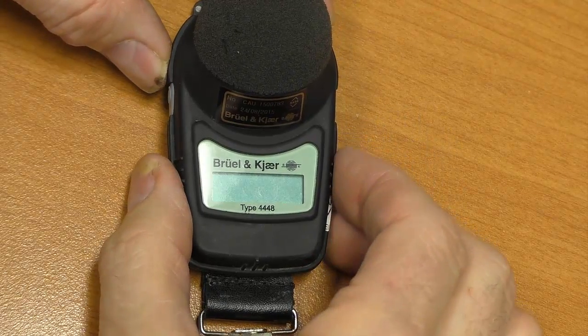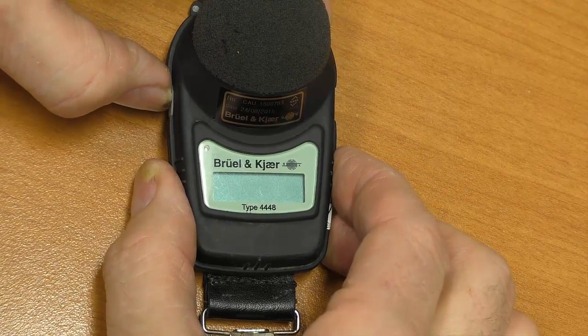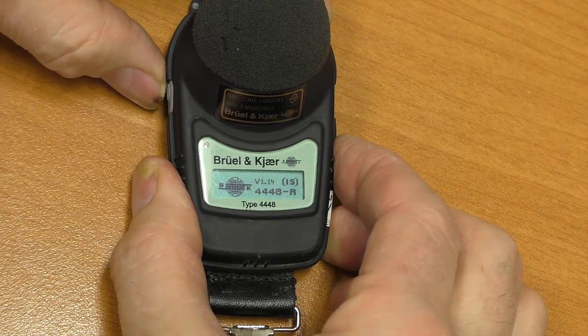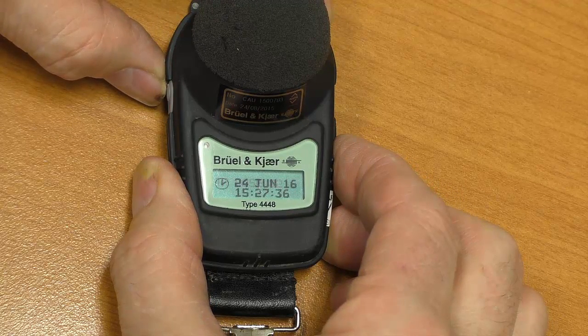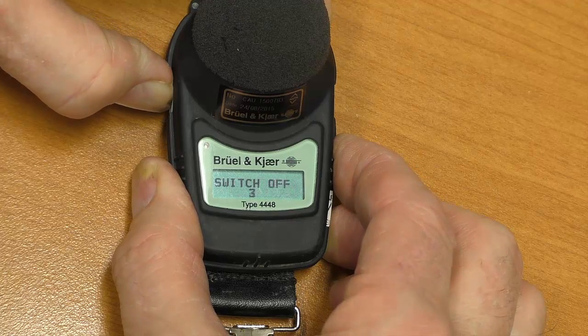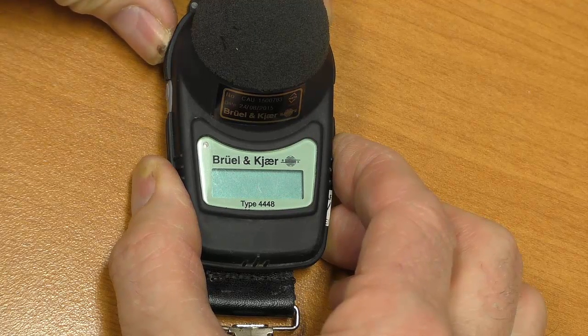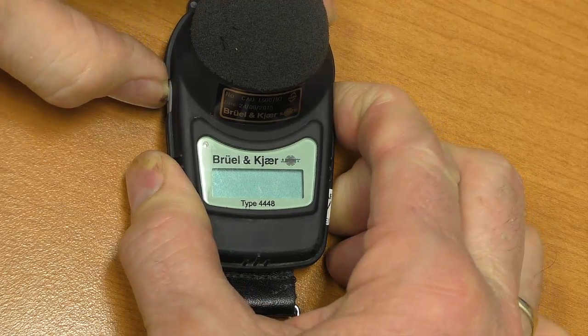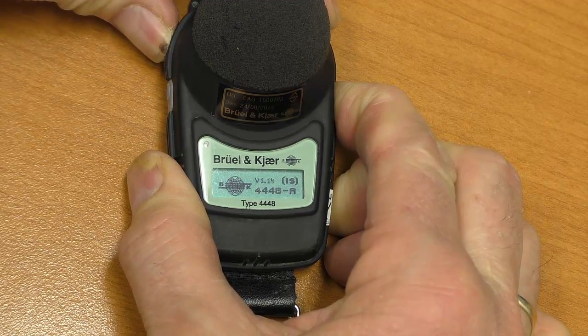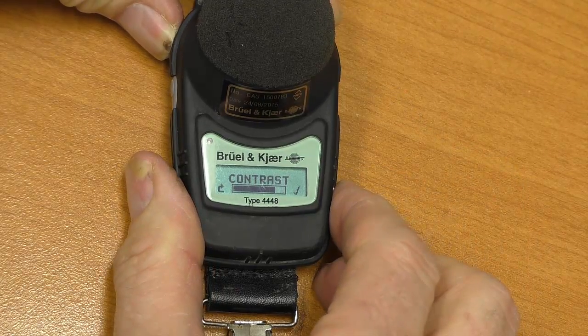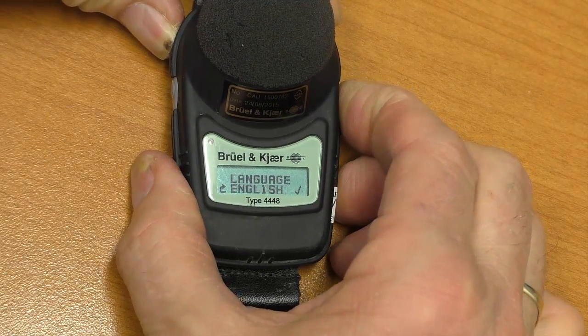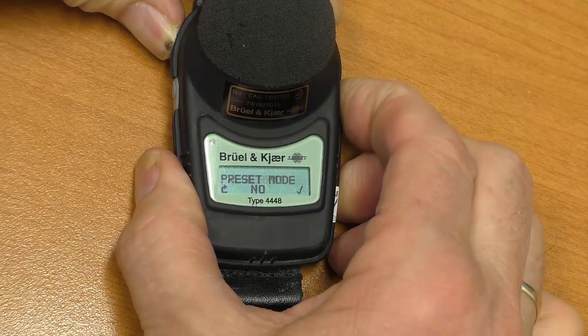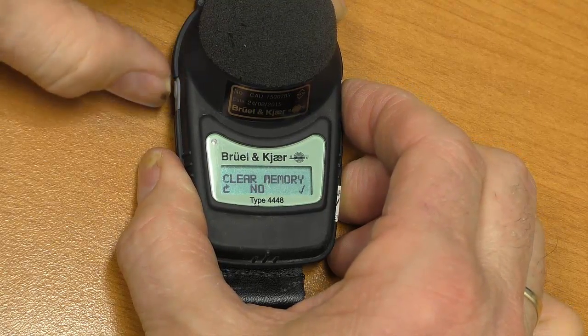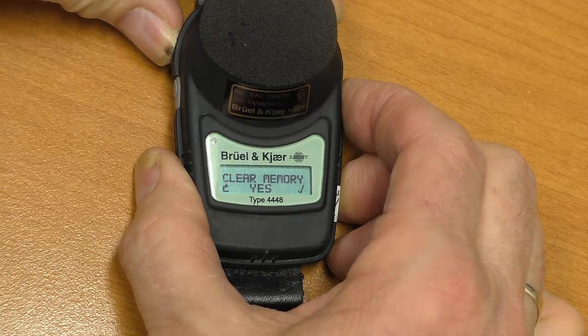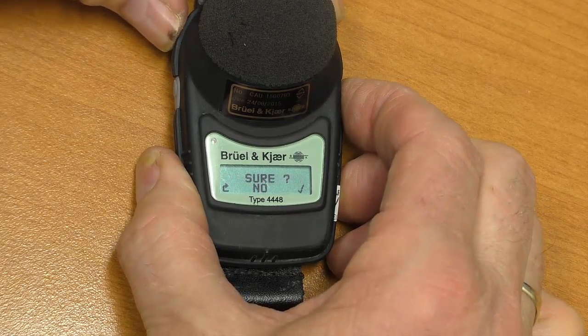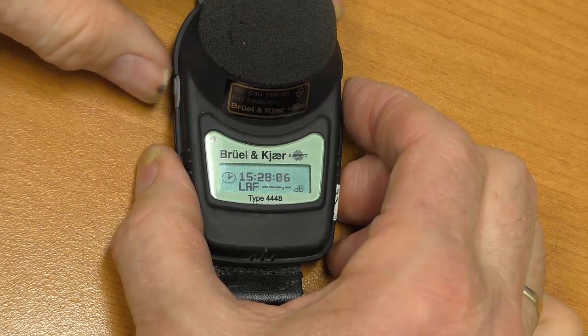All right, now we'll just go through how to operate the instrument. To turn it on, we press this left key. To turn it off, we hold the left key in. To clear the memory, we hold the right key in and push the left key, which turns it on and drops it to a configuration mode. Now we can push the right key and scroll through the various settings until we get to clear memory. The left key switches that to yes, and the right key confirms. Now we've cleared the memory.